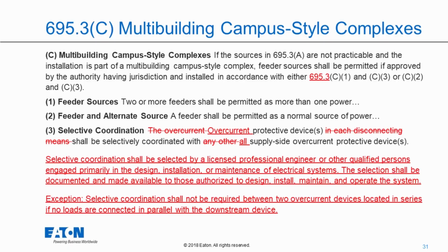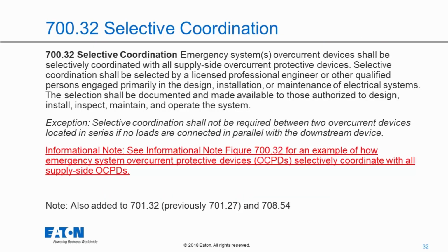And we have that exception I mentioned earlier about the performance. So here we say selective coordination shall not be required between two overcurrent devices located in series if no loads are connected in parallel with a downstream device. So that's really the performance language. The other example in Article 620 gave more specific instances. This would be covered by this single performance exception.